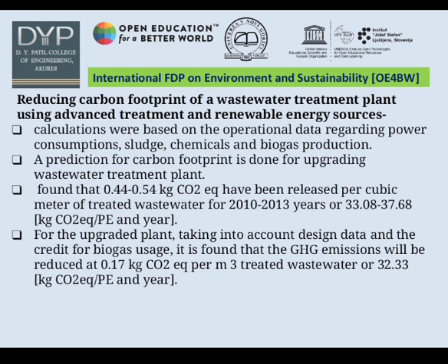In this slide, reducing the carbon footprint of a wastewater treatment plant using advanced treatment and renewable energy sources. Here, the calculations were based on operational data regarding power consumption, sludge, chemicals, and biogas production. In this case, for the upgraded plant, taking into account design data and the credit for biogas usage, it is found that the GHG emissions will be reduced to 0.17 kg CO2 per cubic meter of treated wastewater, or 32.33 per year.